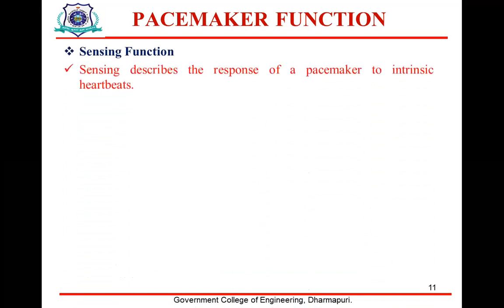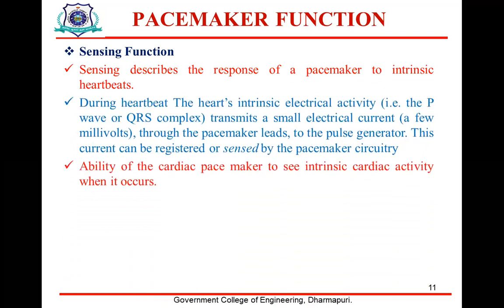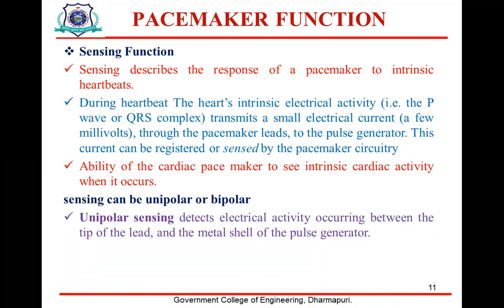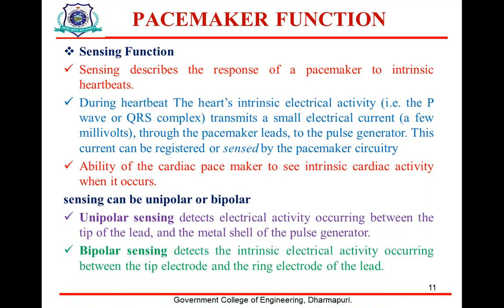The sensing function describes the response of the pacemaker to intrinsic heartbeats. During a heartbeat, the heart's intrinsic electrical activity, which you already studied in the ECG, the P wave or QRS complex, transmits a small electrical current, a few millivolts, through the pacemaker leads to the pulse generator. This current can be registered or sensed by the pacemaker circuitry. This is the ability of the cardiac pacemaker to sense intrinsic cardiac activity when it occurs. The sensing may be bipolar or unipolar. Unipolar sensing detects the electrical activity occurring between the tip of the lead and the metal shell of the pulse generator. Bipolar sensing detects the intrinsic electrical activity occurring between the tip electrode and the ring electrode.